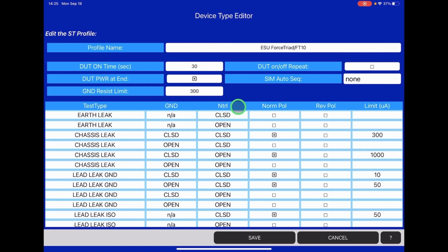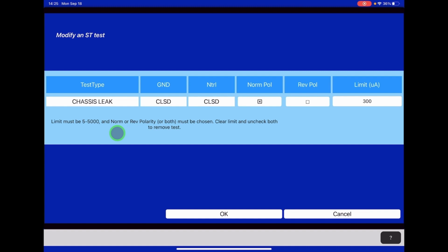So you can select what fault you're going to run. You could also do it in normal polarity and reverse polarity. And over here to the right, you would set your pass-fail limit. For the purposes of this FT10, we're going to run a chassis leakage test. It gives us the option to run earth leakage or chassis leakage. We're going to run chassis leakage tests in normal conditions with both the ground and neutral closed. We're going to do it in normal polarity, not necessary to do reverse polarity, so we're going to leave that off, and we've set the limit to 300 microamps.